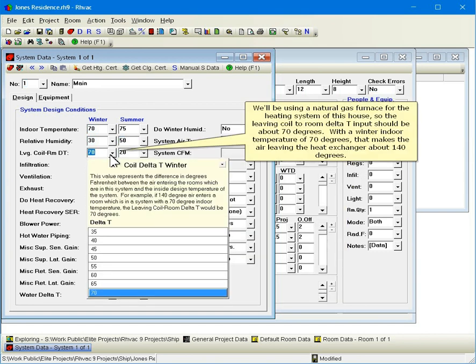We'll be using a natural gas furnace for the heating system of this house, so the leaving coil to room delta T input should be about 70 degrees. With a winter indoor temperature of 70 degrees, that makes the air leaving the heat exchanger about 140 degrees.